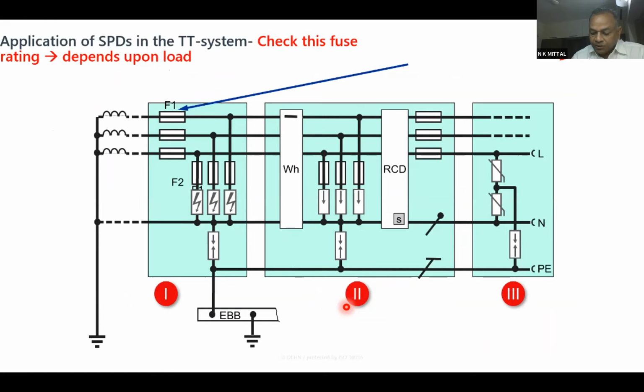Point number 3. The latest NBC code says we have to use SPDs which can withstand, in case of a neutral disconnection, 440 volts for at least 2 hours. This is what the code says, NBC 2017. The fifth question which I have is, suppose there is a building and ours is a large plant comprising a few buildings, maybe 3, 4, 5, 6 buildings. So every building is to be treated independently in the same fashion, that there could be a lightning strike in any other building. So whatever goes inside, the first point of entry has to be protected with a 100K system, because there is a possibility of 100K coming back into the system.